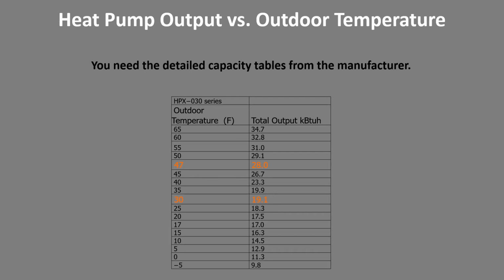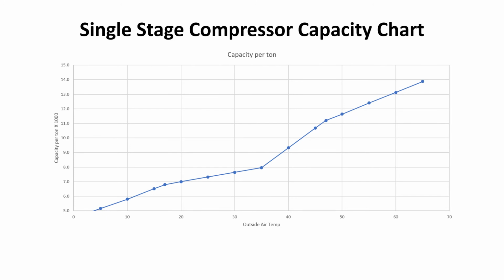This is a detailed capacity from a manufacturer. Some of you might recognize the brand. This is interesting. It's a 2.5-ton unit, and at 47 degrees, their 2.5-ton unit gives you 28,000 BTUs. Not exactly a 2.5-ton machine, but close to it. It's like a 2x4. It's a nominal value, and we should always look at the detailed capacity table.